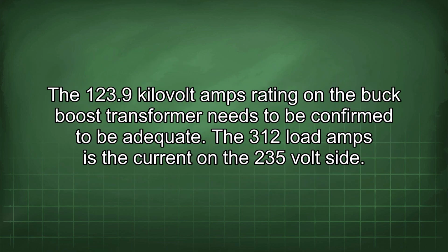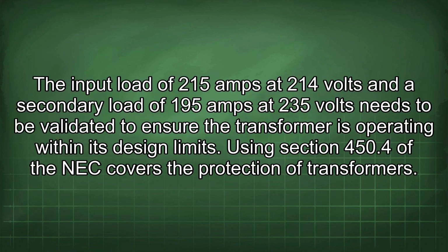The 123.9 kVA rating on the buck boost transformer needs to be confirmed to be adequate. The 312 load amps is the current on the 235 volt side. The input load of 215 amps at 214 volts and a secondary load of 195 amps at 235 volts need to be validated to ensure the transformer is operating within its design limits.